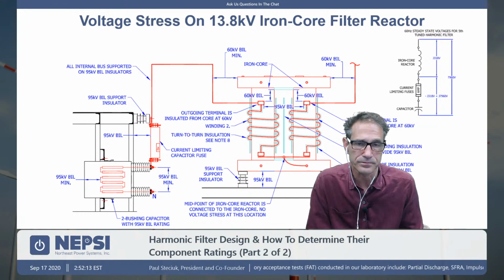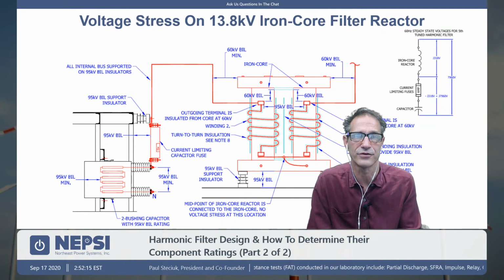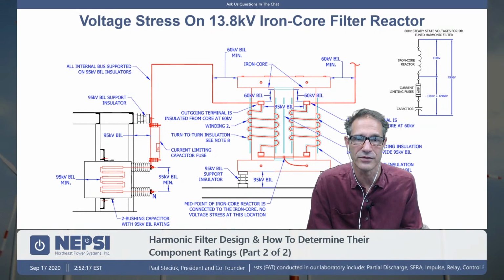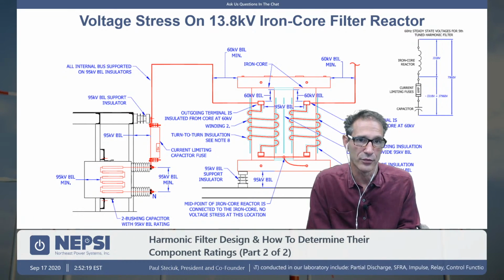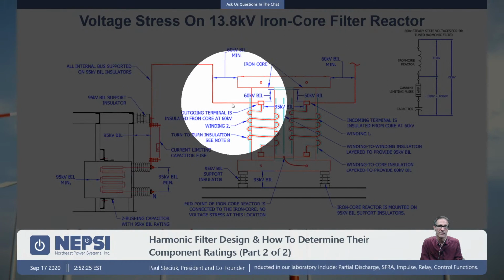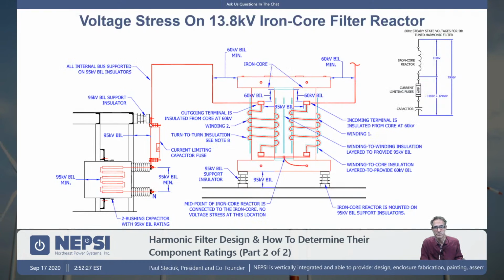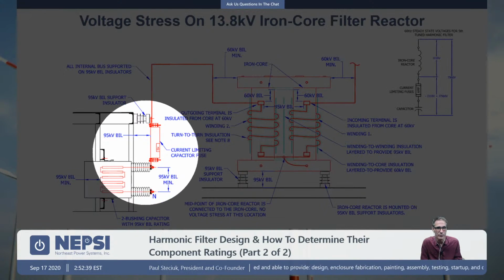So this is a typical voltage stress diagram for a 13.8 kV system. Here we're just showing we have the end coming here, we have a winding around a reactor core, and it goes to a capacitor. What we're showing here is that the voltage stress from the winding to the core can be much less, and it gains some advantage by tacking the midpoint of the winding to the core itself.